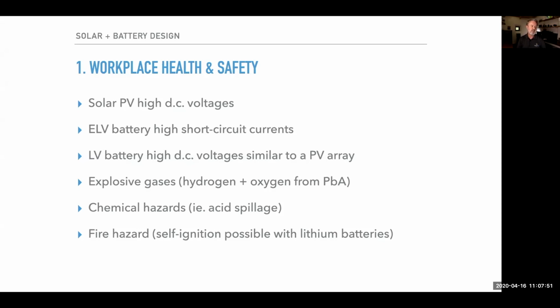And lastly, of course, there are fire hazards associated with some types of batteries. Some battery systems can go into thermal runaway under fault, and that's being considered quite a lot in our new battery standard. For example, it is possible with some chemistries, some types of lithium-ion batteries, and there are many types, that thermal runaway can lead to a fire, and possibly toxic gases. So all of those things have to be considered as part of your safe work method when working with battery storage systems. So how are we going, Rachel?